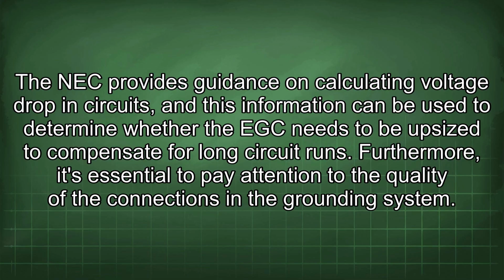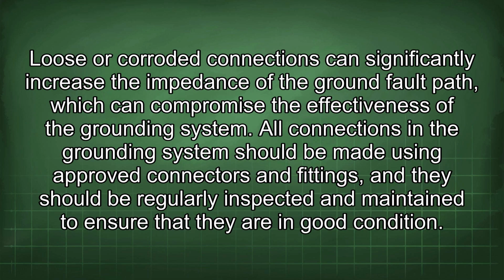Furthermore, it's essential to pay attention to the quality of the connections in the grounding system. Loose or corroded connections can significantly increase the impedance of the ground fault path, which can compromise the effectiveness of the grounding system. All connections in the grounding system should be made using approved connectors and fittings, and they should be regularly inspected and maintained to ensure that they are in good condition.